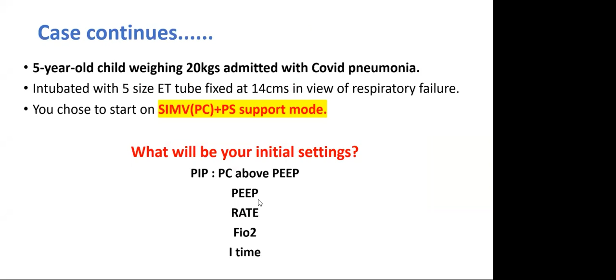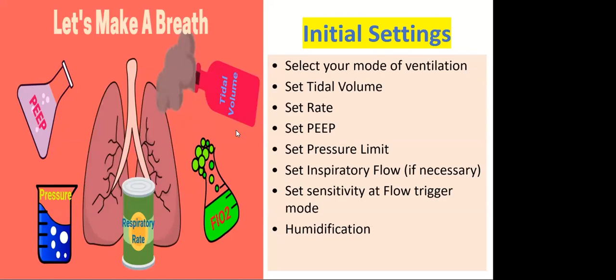So as we already told, pressure control above PEEP you have to set, PEEP you have to set, rate, FiO2 and I time. So how to set that? So let's make a breath. That's what we have to make by putting tidal volume, FiO2, rate, pressure, PEEP, everything. So how to make it? There is no magical number or magic figure that this is the thing you have to follow. So just see pressure limited. If you are putting pressure control mode, you set pressure control above PEEP depending on the lung compliance and pathology.